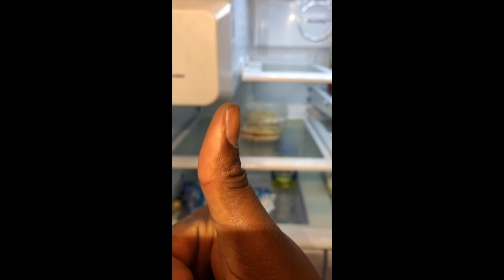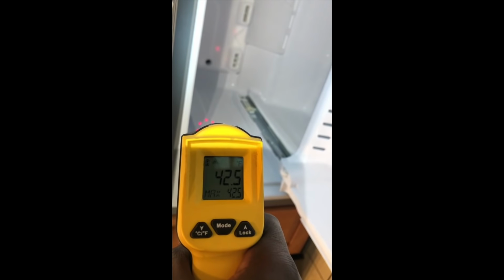Now we're going to check down inside the freezer to see what the temperature is. Pop the freezer door open, stick your temperature probe in there. We got 35 degrees in the freezer. That is bad. Remember, your freezer needs to be 10 degrees and below.